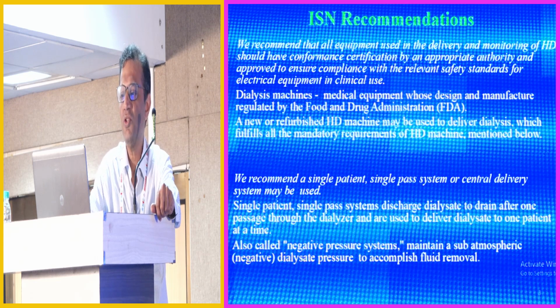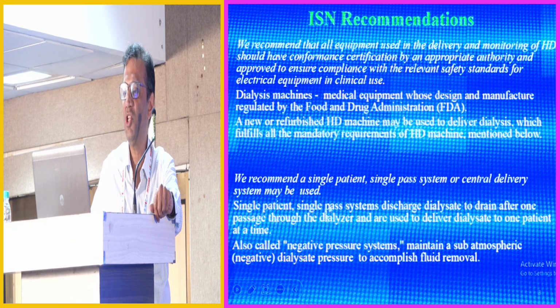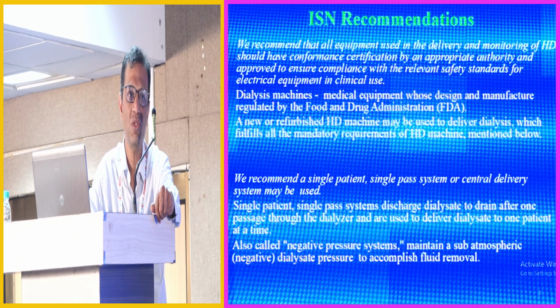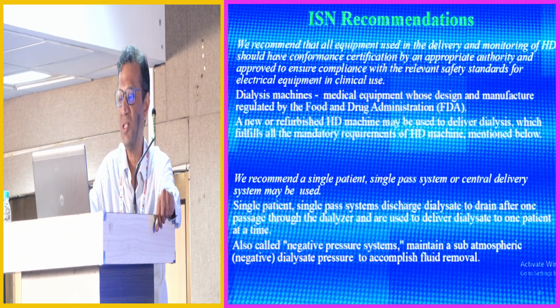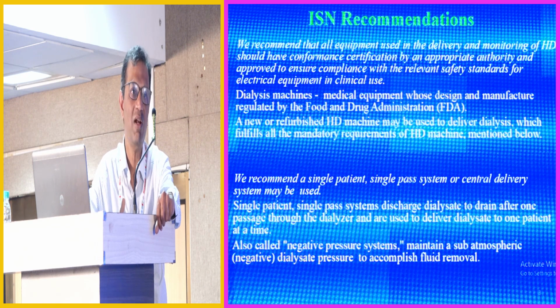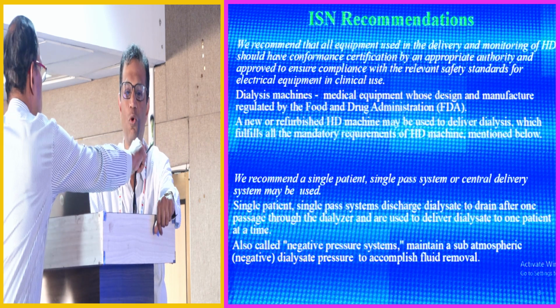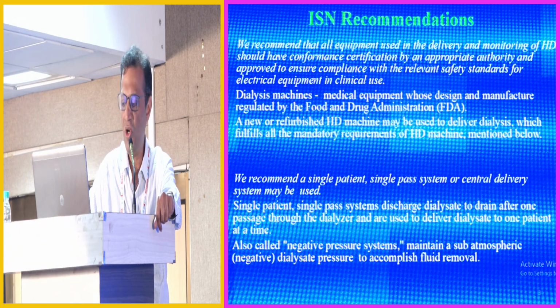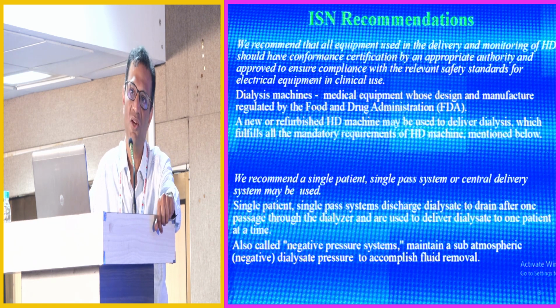So this is what the Indian Society of Nephrology says about machines, that any dialysis machine being used needs to be certified and needs to conform to standards by an appropriate authority, which is the FDA, and in Europe it would be the ISO, which has more stringent guidelines with regard to machines. The machines that we typically use in India, the other machines are slowly coming in, are what are called single pass machines. That is, the dialysate comes from the machine, goes to the dialyzer, back to the machine, and goes to the drain. And they are also called negative pressure machines, as opposed to many years ago the Travenol was a positive pressure machine.